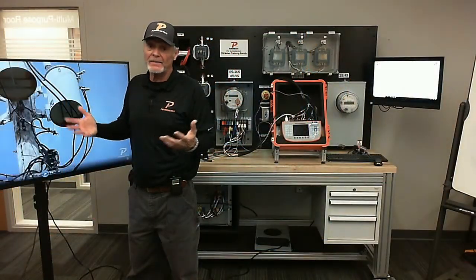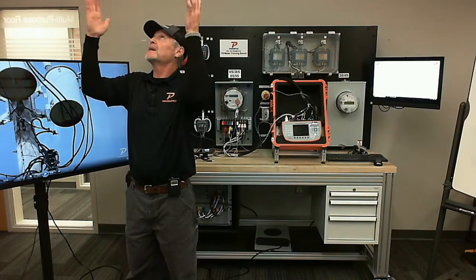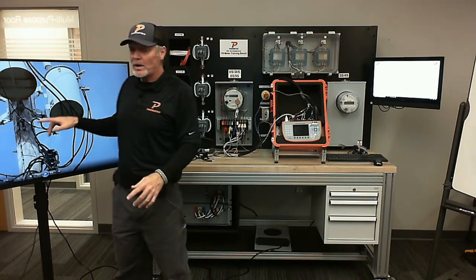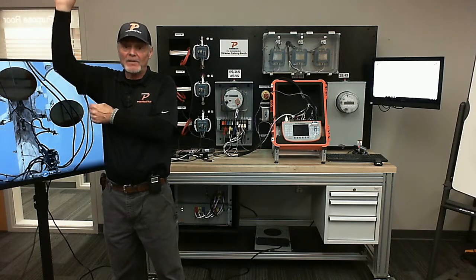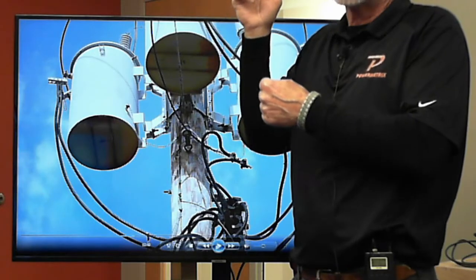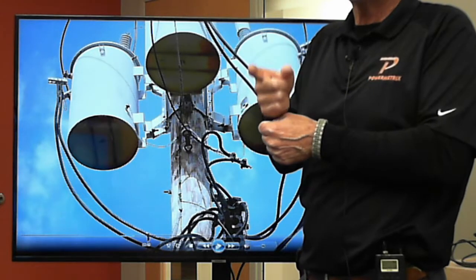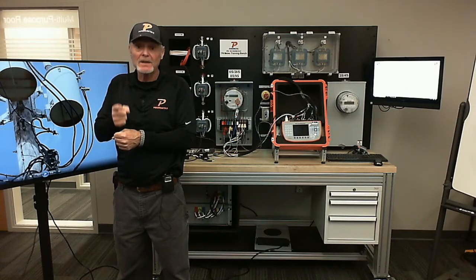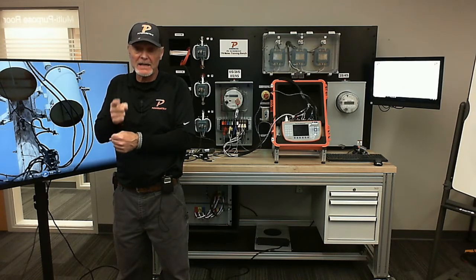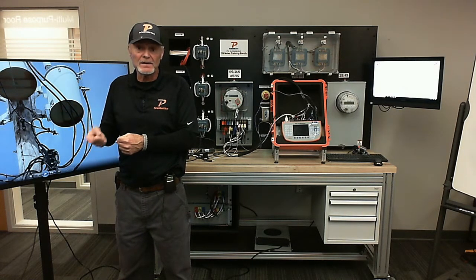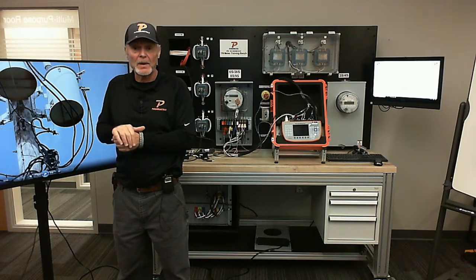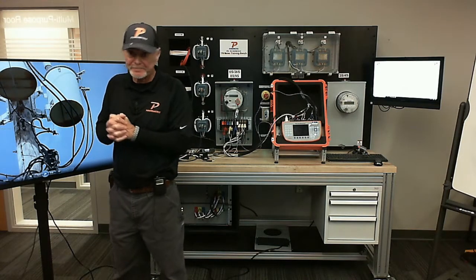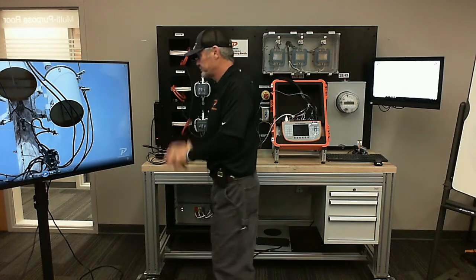It's an easy method: if you're trying to figure out which phase is at the top of the pole, just grab one of the outside phases, put the high volt probe on it, and start the test. If you get a cross phase error, you know you're on C instead of A, since the machine starts out testing A phase. So if it gives cross phase, you're on C instead of A, and you can go from there. That way you've determined what phase is what at the top of the pole, since it's not always labeled well.